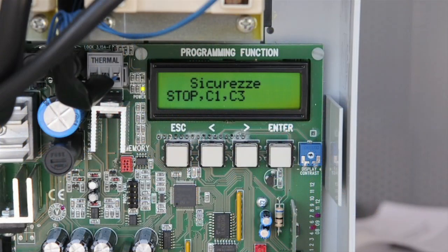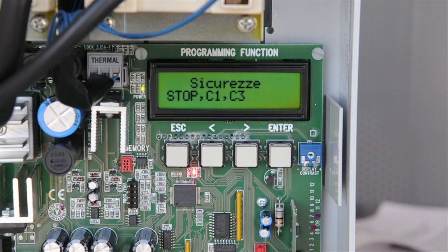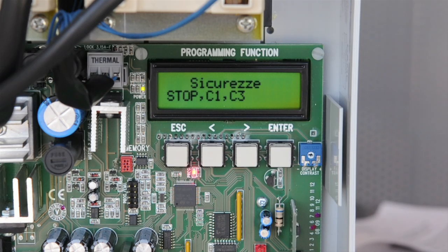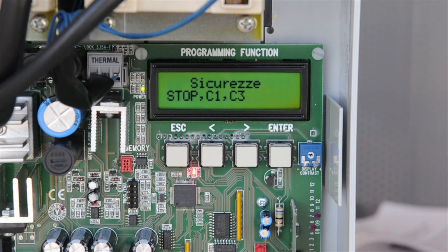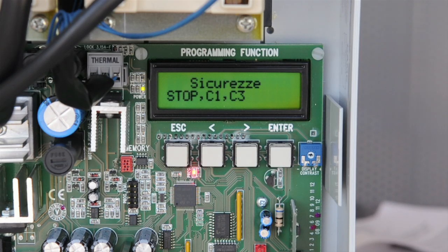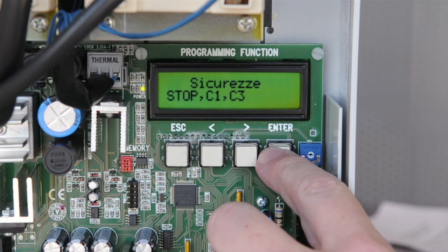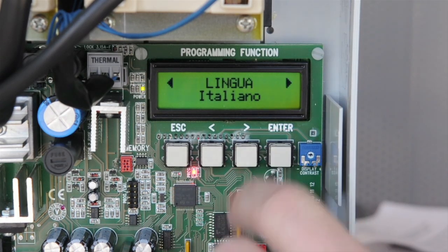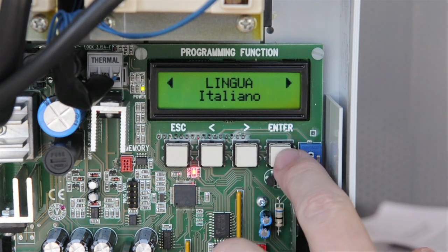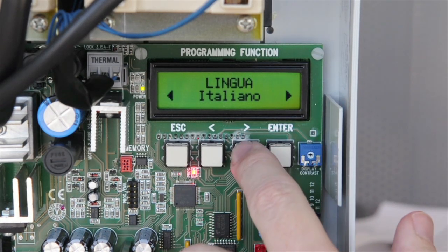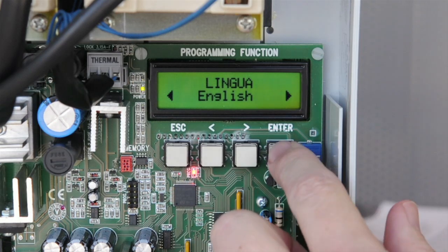When powering up for the first time, the default language is Italian and there are three errors that must be cleared: Stop, Safety C1, and Safety C3. To set the language, press and hold the enter button for one second to enter programming mode. Select language and choose English.